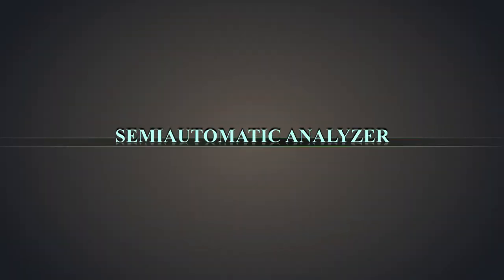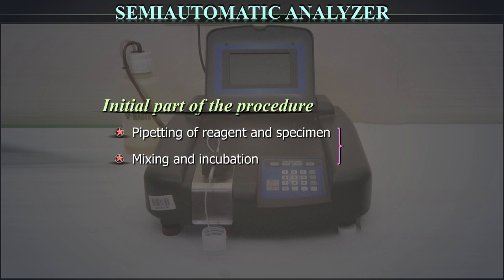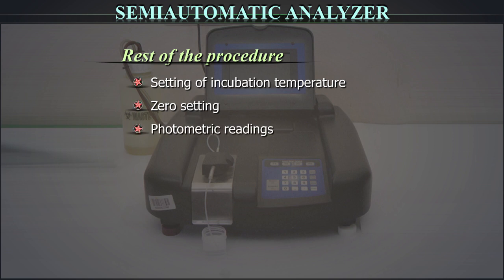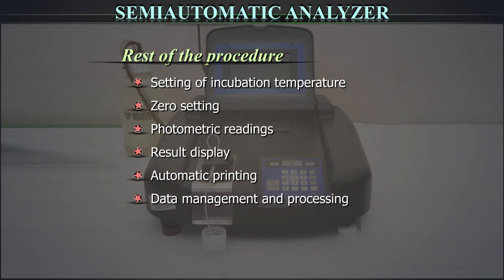The Semi-Automated Analyzer, as the name implies, has partial automation. The initial part of the procedure, i.e. pipetting of reagent and specimen, mixing and incubation, is carried out by the technician. The rest of the procedure, i.e. setting of incubation temperature for kinetic determinations, zero setting, photometric readings, result display, automatic printing and data management and processing, is carried out by the analyzer.